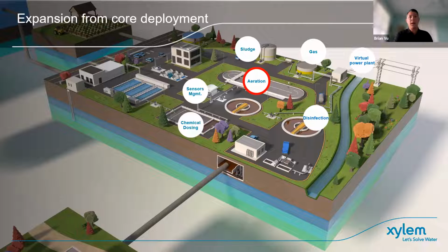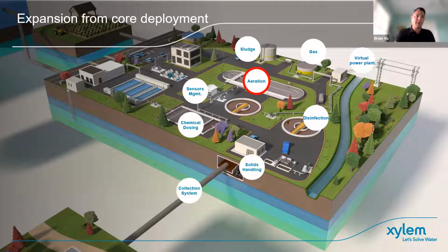Chemical dosing as well—maybe adding iron salt or metal salt for phosphorus removal. Controlling dosages on chemical dosing is important for reducing costs and overusage. Solids handling is the same type of thing: we've got polymer we're dosing, and we can automate polymer systems, dewatering equipment, and centrifuge equipment—those are all things to look at for automation. In collection systems, lift station automation is key: when to turn pumps on, rotating pumps, keeping a steady flow within the system, that can all be automated. Then in pre-treatment, there's a lot of automation too—grit removal, grit cleaning, and screens can definitely be automated to remove debris coming into the plant. No one wants to spend a whole day running this by hand.